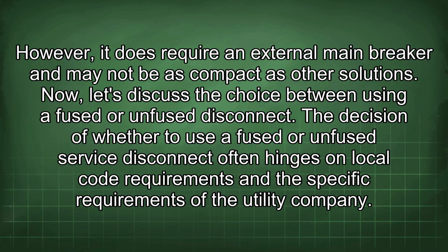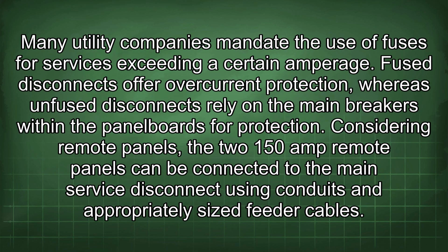Now, let's discuss the choice between using a fused or unfused disconnect. The decision of whether to use a fused or unfused service disconnect often hinges on local code requirements and the specific requirements of the utility company. Many utility companies mandate the use of fuses for services exceeding a certain amperage. Fused disconnects offer current-limiting protection, whereas unfused disconnects rely on the main breakers within the panelboards for protection.